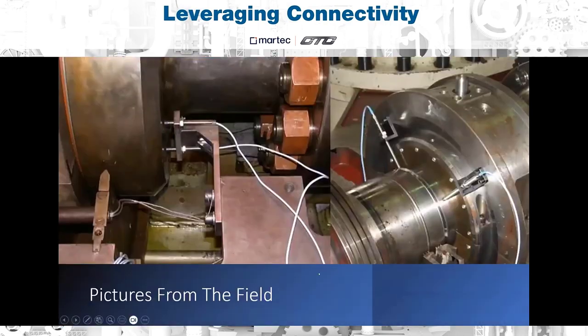So the 2 most common applications for proximity probes are the radial and axial monitoring of machines utilizing journal bearings. Over here on the left, you can see 2 probes that are facing the collar of a shaft. This is a great way to measure thermal expansion, as well as any kind of thrust measurements that may be happening on the shaft. Many times they will use 2 probes for redundancy's sake. And oftentimes these probes will be used to shut down the machine if it comes out of position, because if this shaft gets in contact with the machine housing, it can often lead to catastrophic failures.